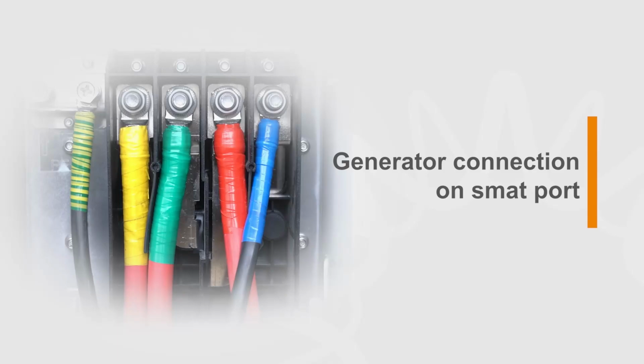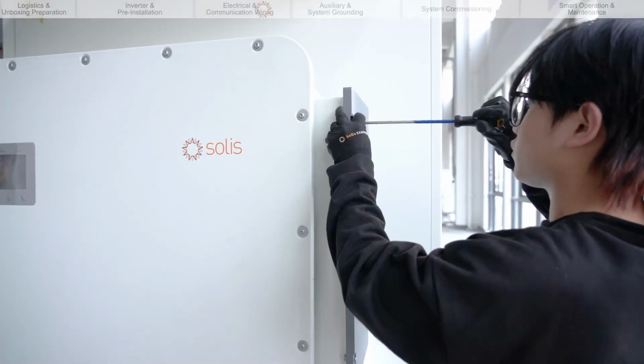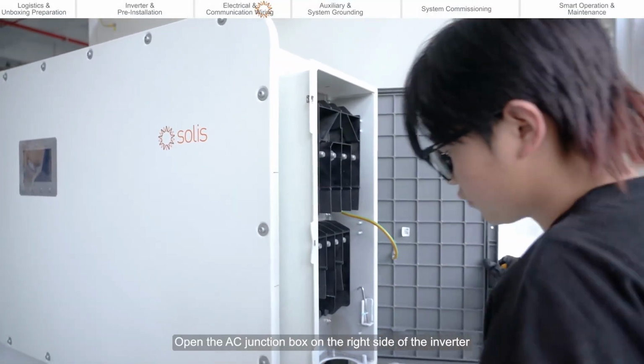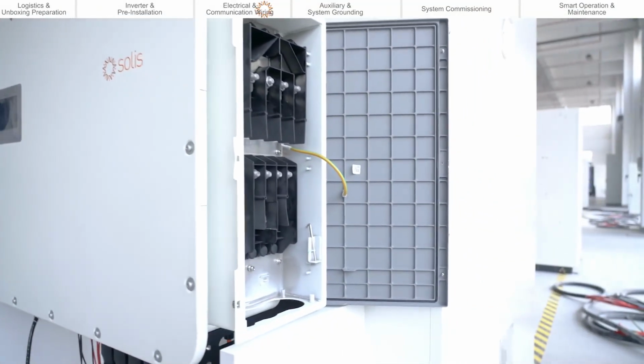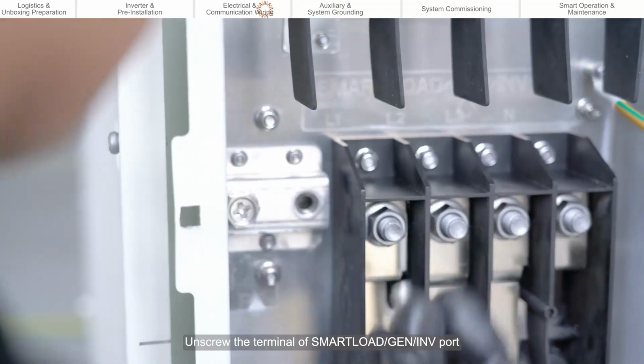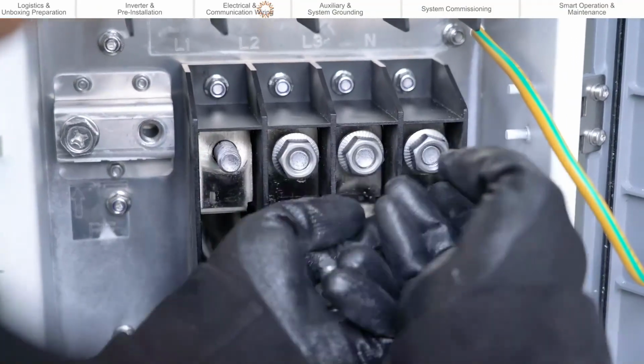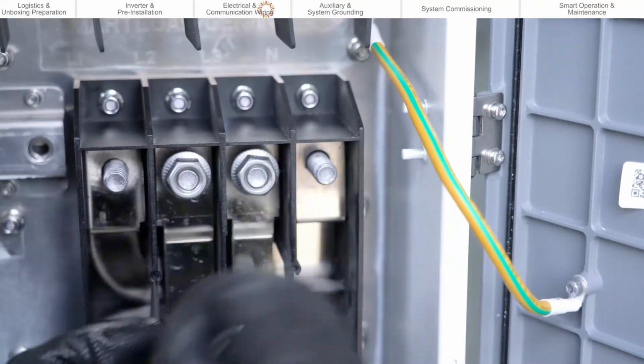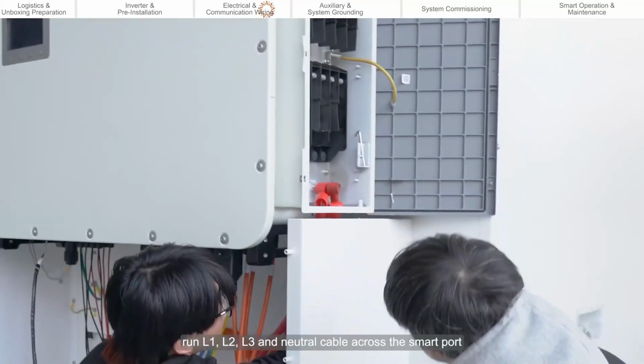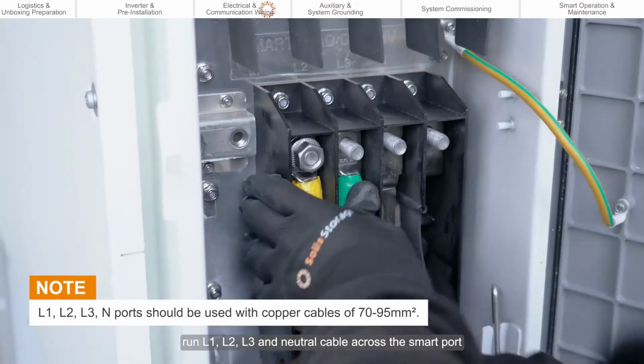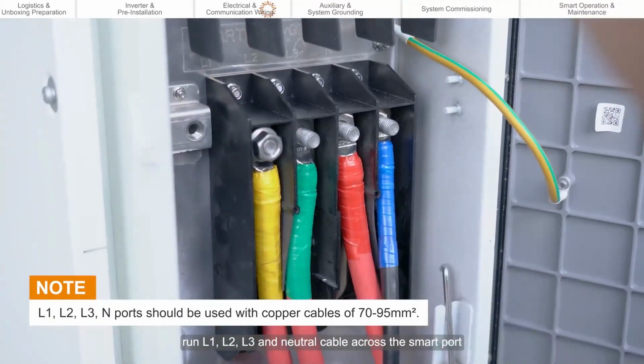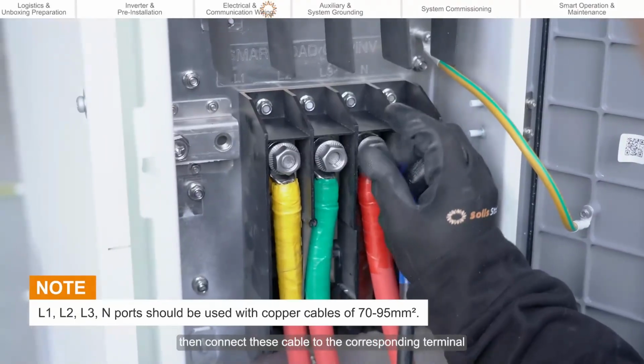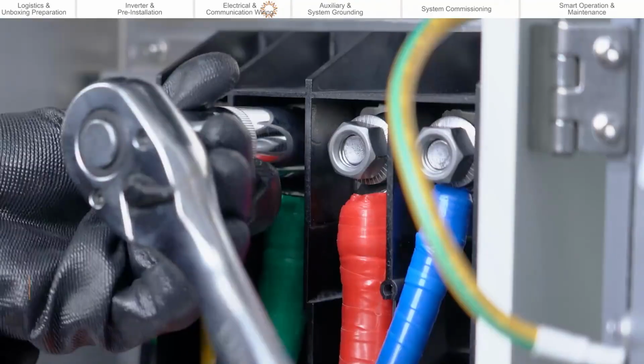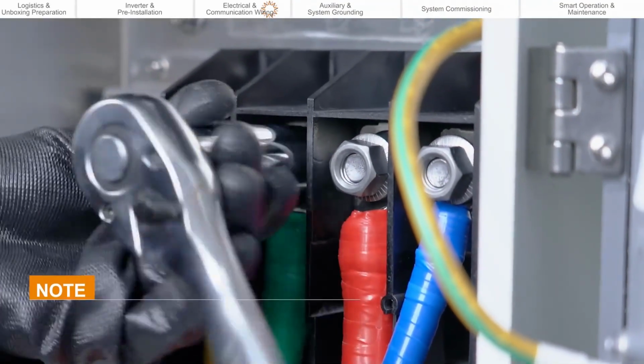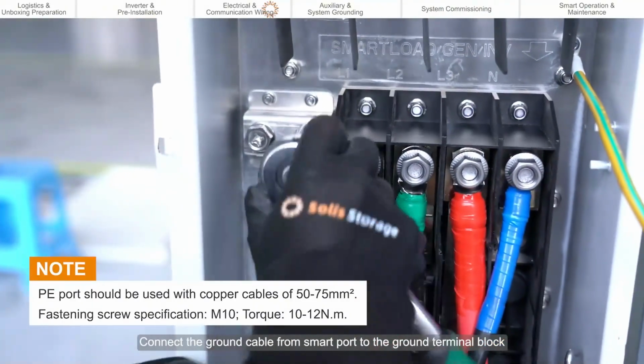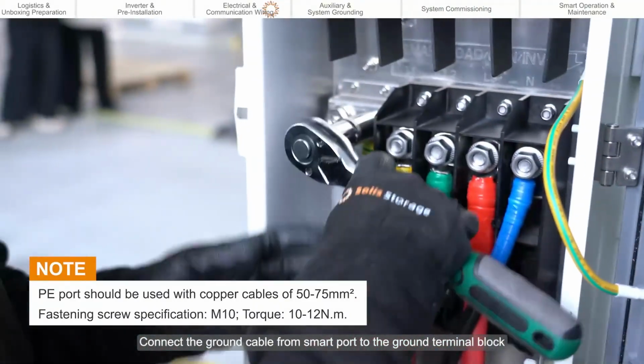Generator connection on SMAT port. Open the AC junction box on the right side of the inverter. Unscrew the terminal of SmartLoad, Gen-NV port. Run L1, L2, L3, and neutral cable across the smart port, then connect these cables to the corresponding terminal. Connect the ground cable from smart port to the ground terminal block.